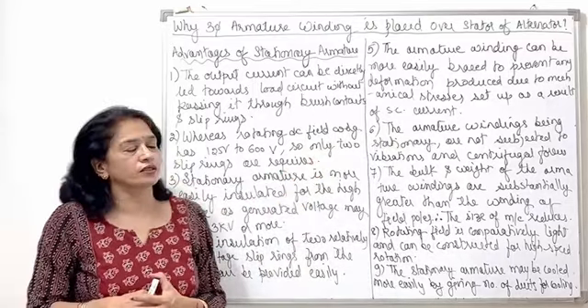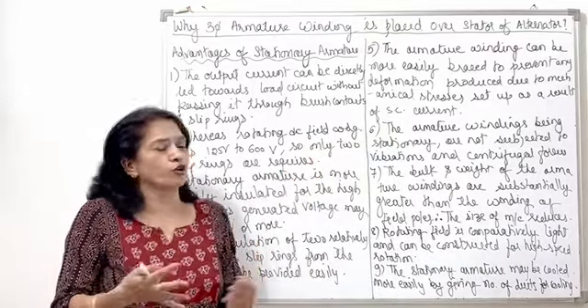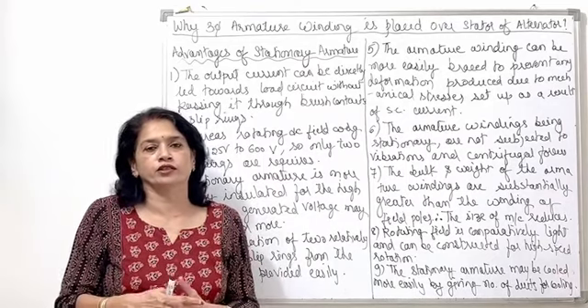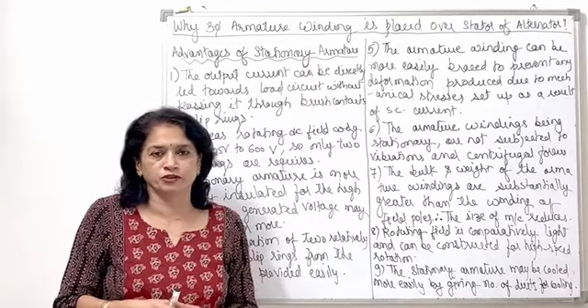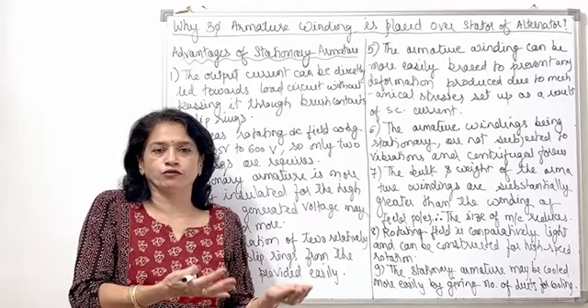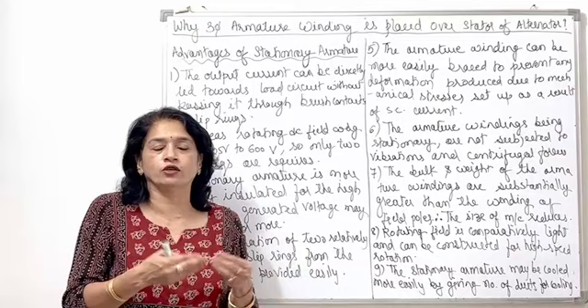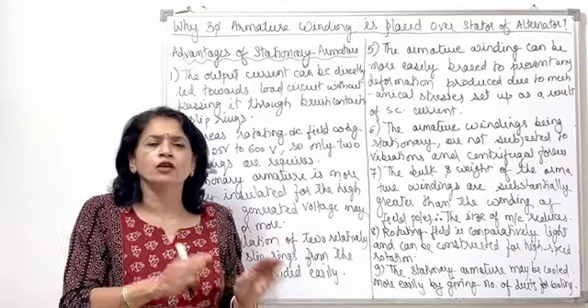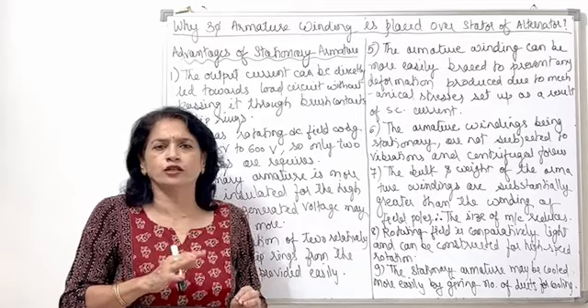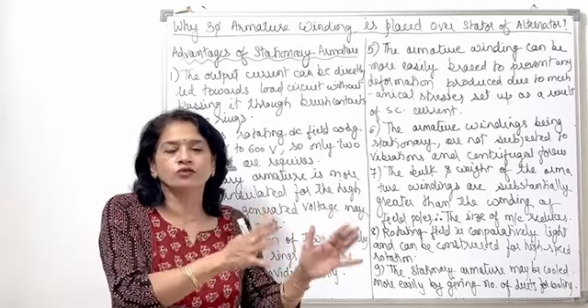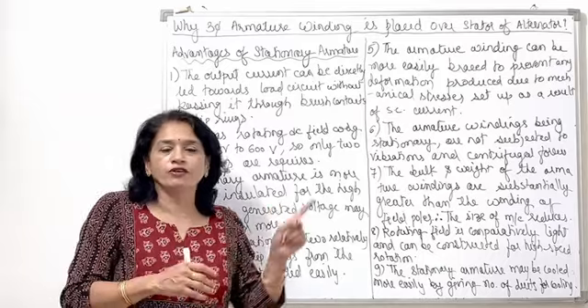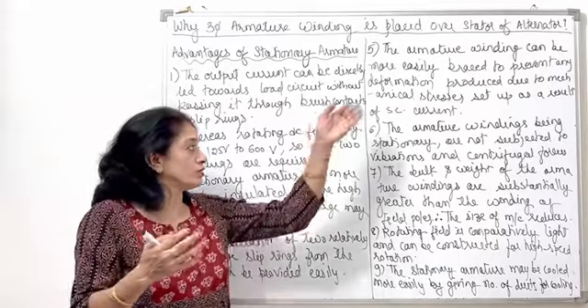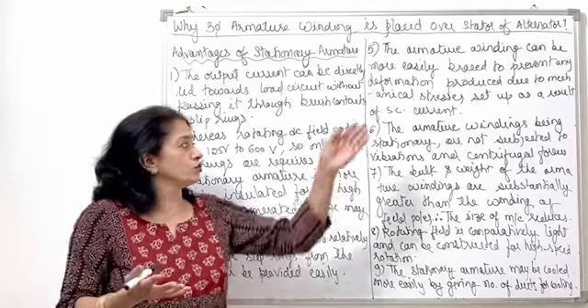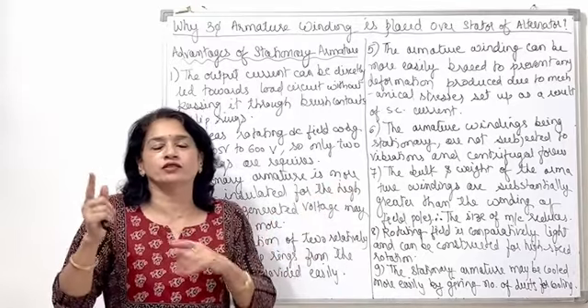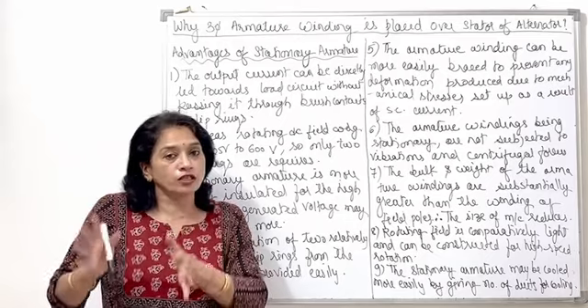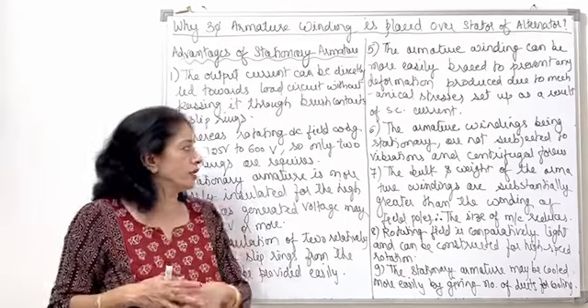Next, armature windings can easily be braced against the deformation produced by the large short circuit currents due to the different faults occurring in the power system. If the system which has to carry the large fault current or short circuit current is stationary, then whatever stresses are developed due to that large current are manageable. If it had been provided over the rotor, difficulty could arise due to high currents producing stresses in that rotating high voltage three-phase circuitry. That would be very cumbersome to handle.